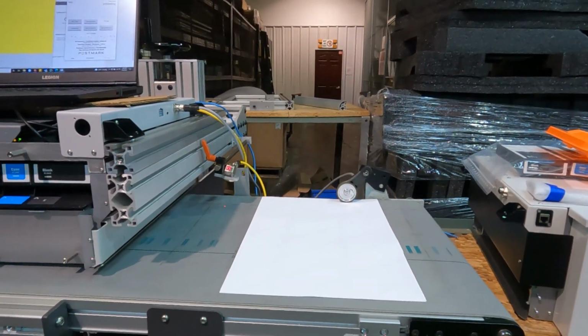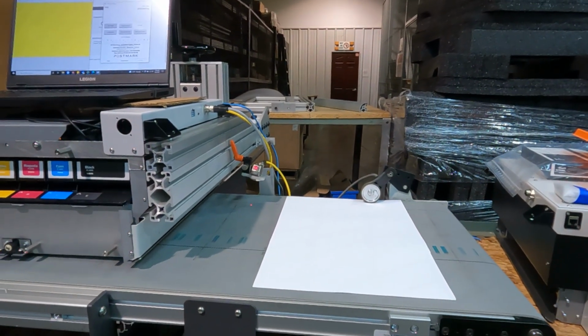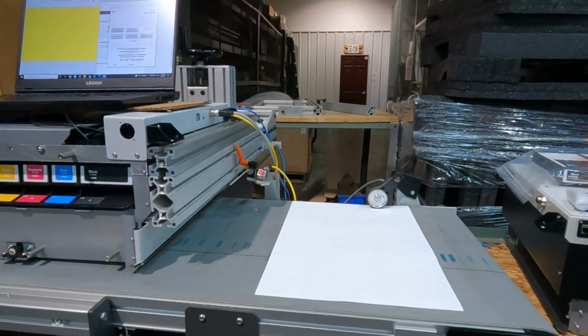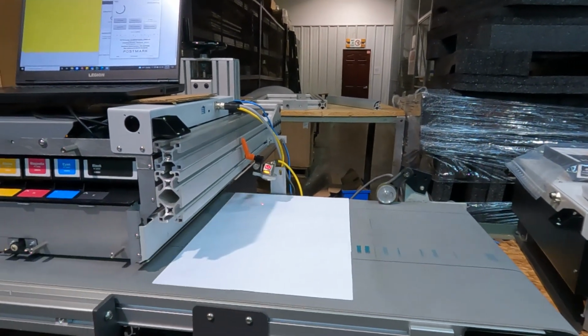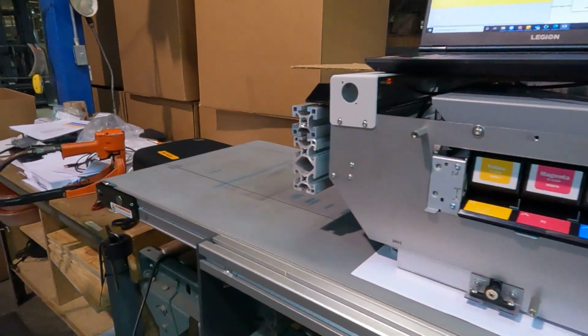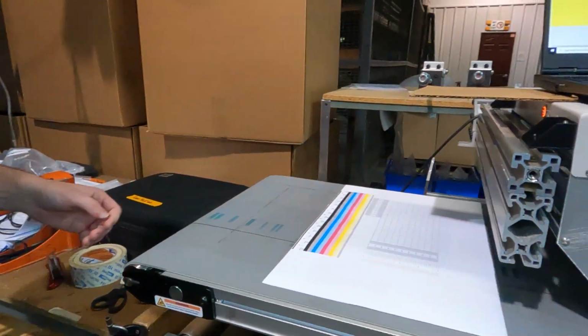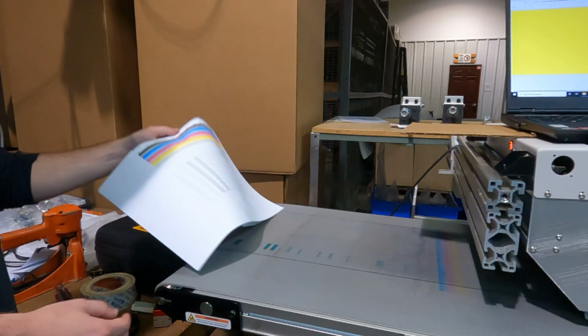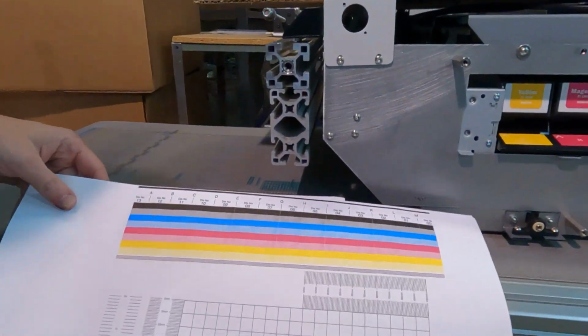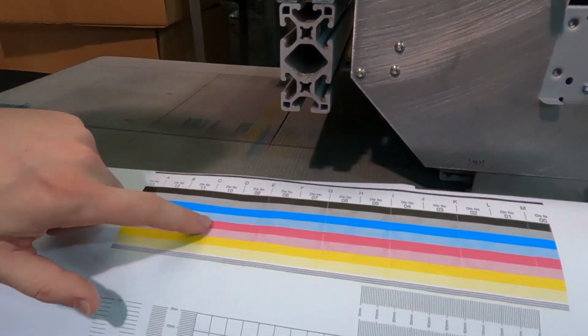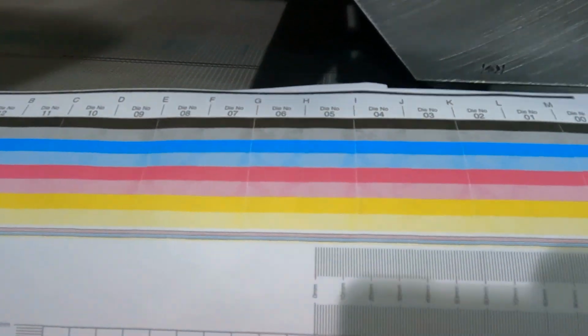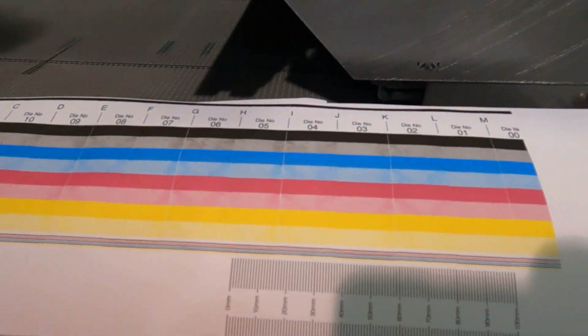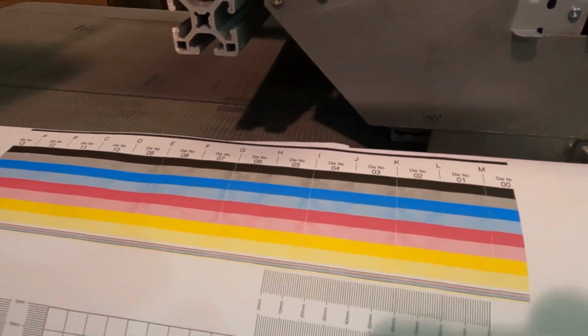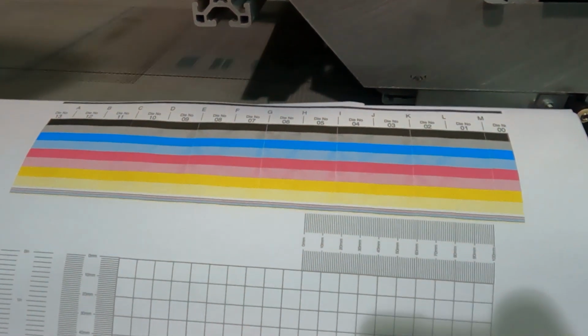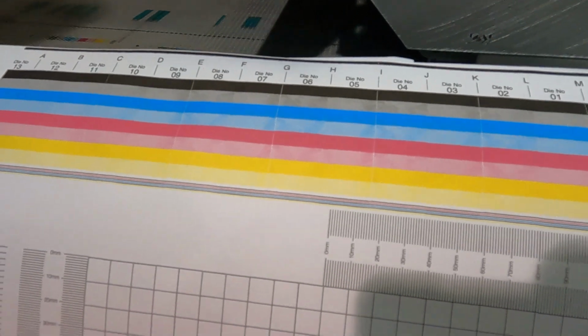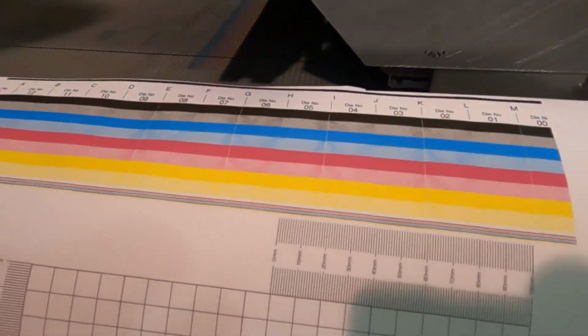So quick hold, test print. It's looking better. We do have these gaps between our dies, and that's just a matter of calibration. So we'll go into calibration really quickly. This needs to be done at the customer's end anyway, so we're not going to go too crazy trying to get these closed up, but we'll at least walk through how to do it.